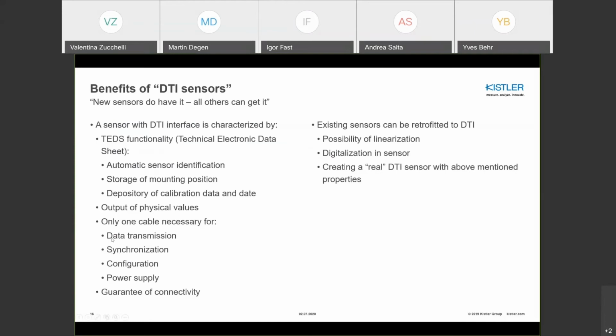As I mentioned before, the data transmission, synchronization, configuration, and power supply are all done with one cable, and you will receive really physical values from your sensor. So you do not have to recalculate millivolts per volts in your data acquisition system. If you plug in a sensor with our DTI system, you will get newtons, kilometers per hour, or whatever the sensor is delivering, in the right standard international unit.